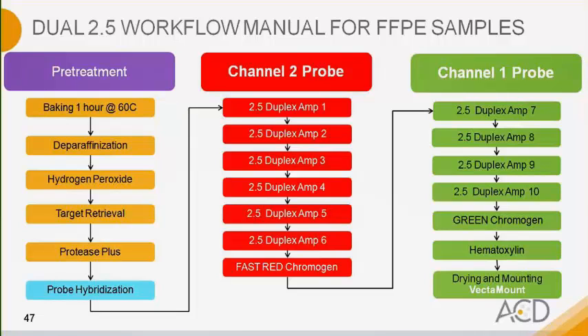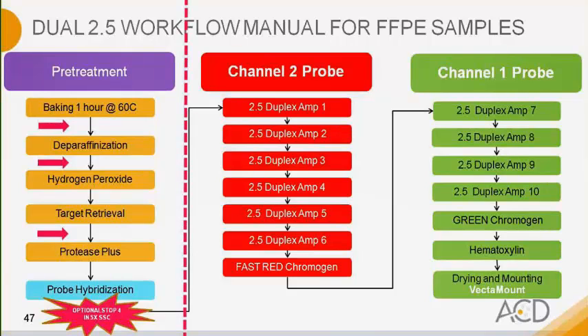Following this, the first channel is amplified to yield the red signal, and then the second channel is amplified to yield the green signal. Now there are multiple stopping points to allow you to run the assay as per your convenience. You may stop after baking, deparaffinization, and target retrieval for up to 24 hours. It is, however, advisable to complete these steps and stop after the probe hybridization step to split the assay evenly over 2 days. In order to do that, you will require 5x SSC. And lastly, please note that you can split the assay after the probe hybridization step and continue with the channel amplification steps the next day.